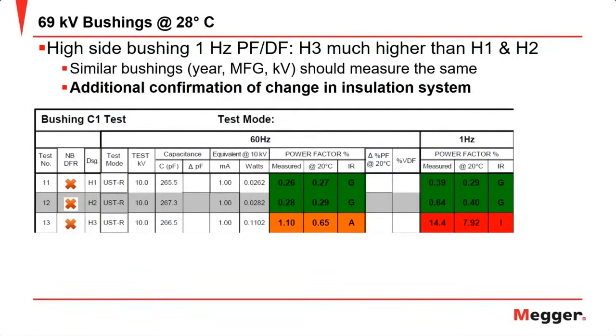And for this transformer, and for many other transformers like it, when it has 3 bushings on the high side, they are typically the same bushing type from the same manufacturer that was built in the same year with the same kV, with the same amp rating. So you would expect that these bushings will age similarly as time goes on. And any changes that are seen in 1 bushing compared to the other 2 is likely due to that insulation changing inside.